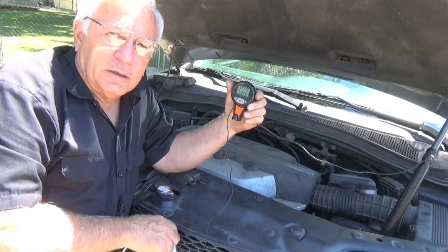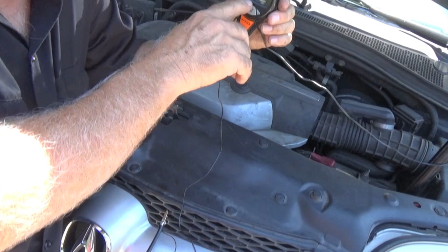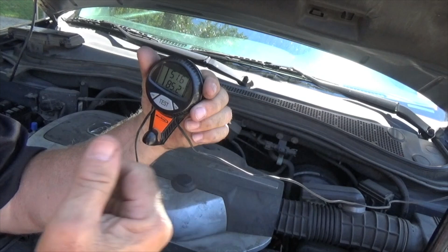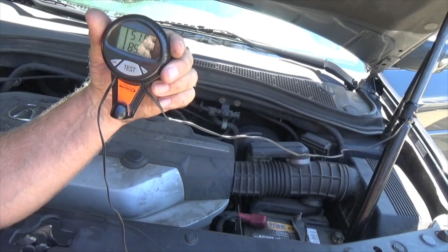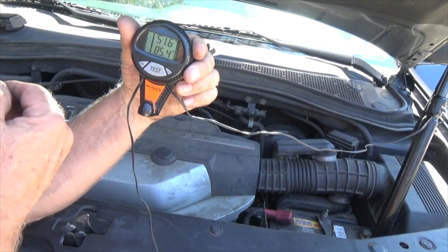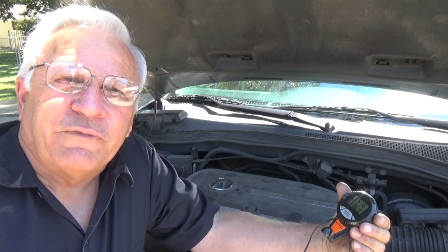If we look at our temperature sensor, my probe right here goes to the front of the vehicle for my outside ambient temperature, and it says it's 85 degrees outside. Now this wire goes in, and I've got another temperature probe on the inside ductwork, and it says the inside temperature with the doors open is 51 degrees. As a rule of thumb, if we get an air conditioning system to drop 30 degrees from outside to inside temperature with the doors open and everything, then it's operating like it should. So again, the key to proper diagnosis is to find the evidence and let the evidence lead you to the problem.